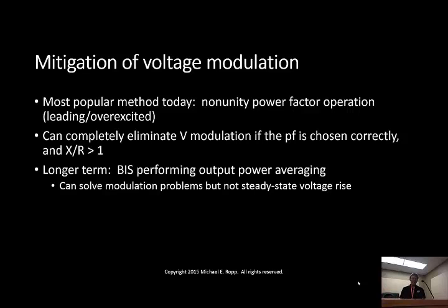We use BIS instead of the IEEE standard BESS, which stands for Battery Energy Storage System, because with BESS, it's not clear whether the inverter is included, whereas with BIS, it's totally clear. So if you have a BIS, then you can have it monitor the power output of the PV plant. And the BIS is controlled so that the power to the grid is equal to the windowed average of the power from the PV plant. So basically just using the BIS as an active power filter. And it smooths the PV output power based on some averaging window.